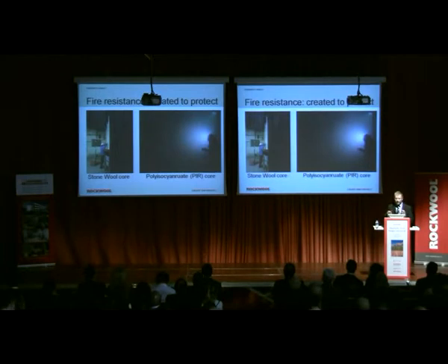If I look now at fire resistance, we expect that fire-resistant walls, partitions, and doors are created to protect people on the other side. If we performed a test on a typical stone wool core sandwich panel and a polyisocyanurate core sandwich panel, you can see the fire resistance testing laboratory and the laboratory operator measuring gaps between the panels, and the same guy measuring something else with polyisocyanurate. This was only a couple of minutes after the start of the fire test.